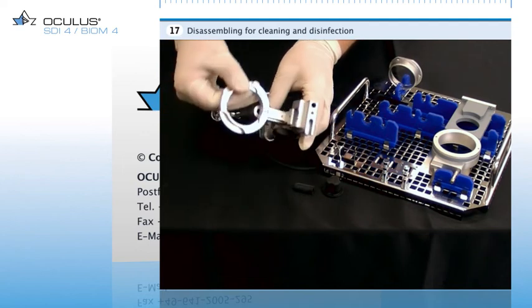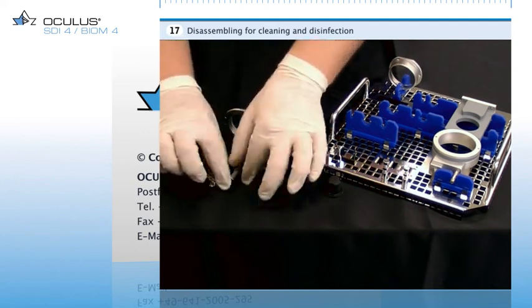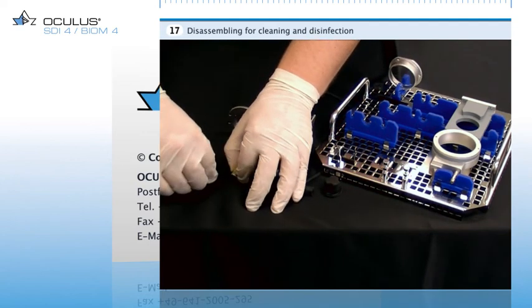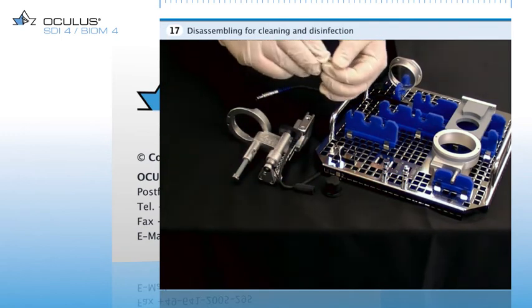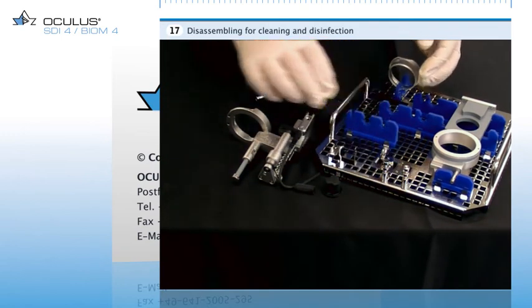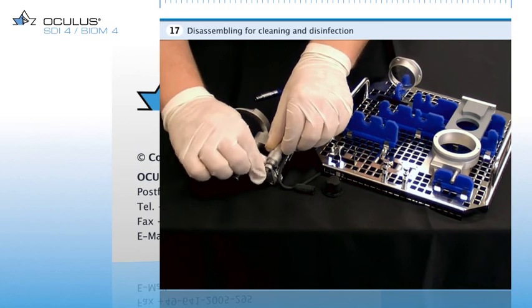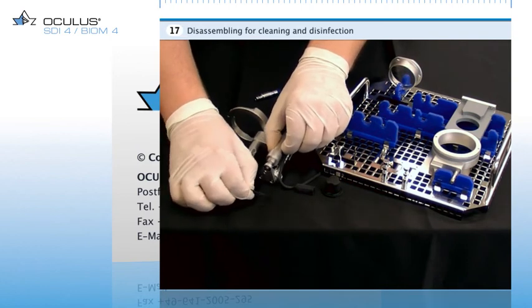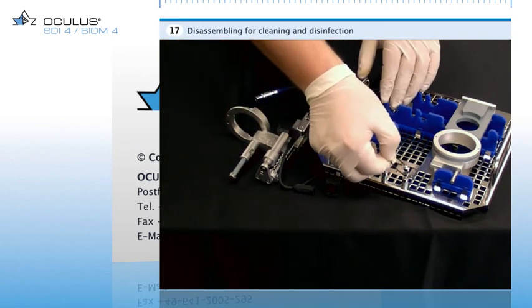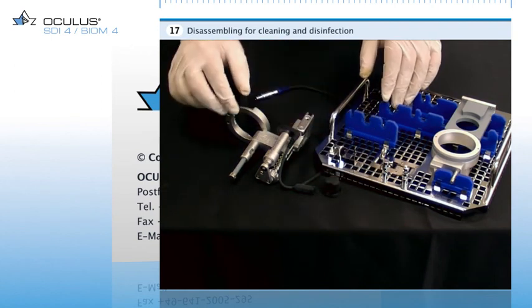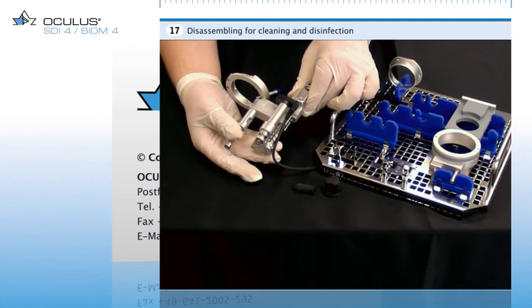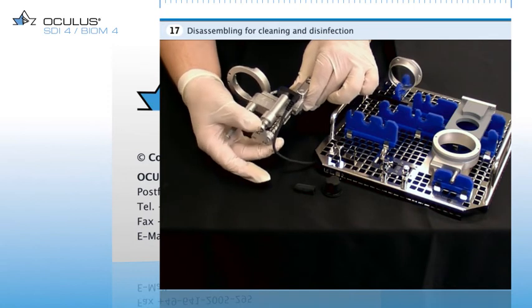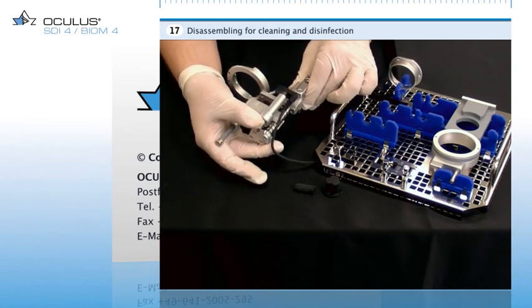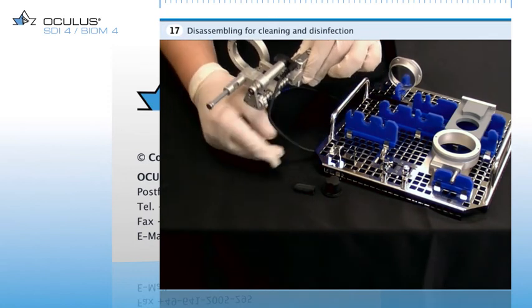Draw the BIOM wide-field front lens forward off the lens holder and place it on one of the mounts of the sterilization tray. Pull the drive belt off the guide rollers of the BIOM and place it on its mount on the sterile insert. For putting the BIOM into the sterilization container, first reduce its length by turning the focus adjustment wheel so that the instrument fits onto its mount on the sterile insert.